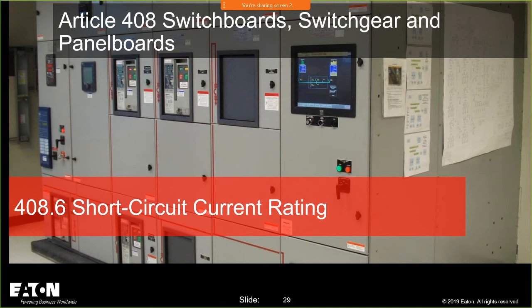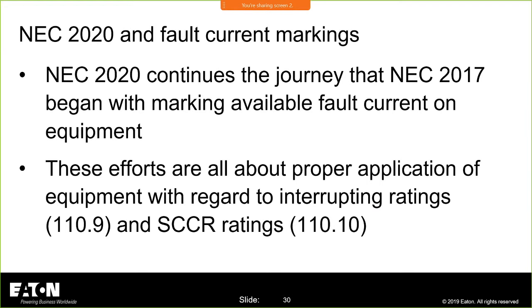So I am going to take this party over to 408. And if we remember, 408 is switchboards, switchgear, and panel boards. 2020, and I know Larry loves when I use this word, journey. NEC 2020 continues the journey that the 2017 NEC began with a marking of available fault current on equipment.